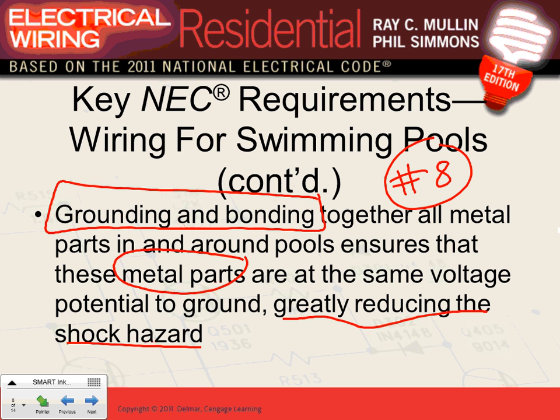If everything is bonded and grounded, the minute that this gets a fault in it and this frame gets energized, if this is grounded, what's going to happen if you bring a hot to a grounded object? What's going to happen to the circuit breaker? It will trip immediately. So imagine all these objects around the swimming pool. If you guys have to remember two things: number one, everything metallic around the swimming pool must be bonded together. Number two, all your receptacles around the swimming pool must be GFCI. And there's a limitation on how far you can go with your receptacles.